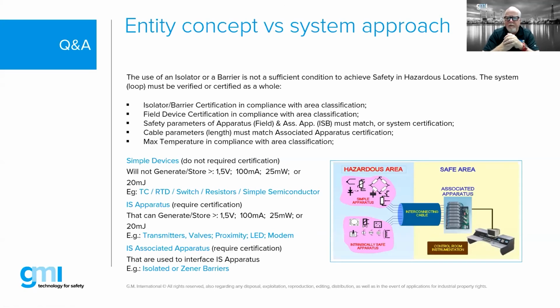In the case of a galvanically isolated barrier, all it's doing is repeating that signal back and forth. The point at which barriers really do their job is when we have a fault, a cut in the cable, a short, something out of the ordinary. That's where the barrier comes into play. Think of it almost like a surge suppressor for your house: under normal circumstances, surge suppressors just sit there, allowing current to flow. But as soon as we get above a certain threshold, they kick on, and that's when we start getting protection. The same holds true with IS barriers.